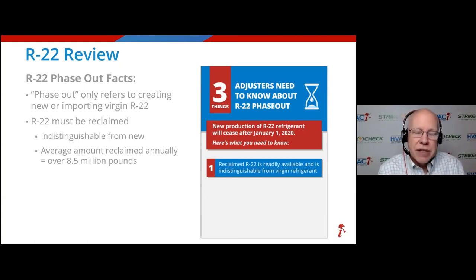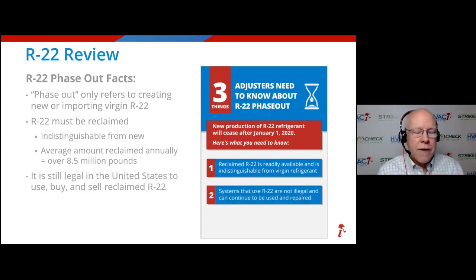So we have a stockpile of R22, 8.5 million pounds a year, as a matter of fact. When we were making it in the United States, we were making about 4 million pounds a year. So we've been reclaiming it higher than making it, even back when we were making it. Per the Montreal Protocol, and this is the kicker right here, it's legal to use, buy, and sell reclaimed R22. All right? We can get it. So when they say they can't get it, they either don't want to get it, they're not looking hard enough, or they want to sell a new system. It's available and you can get it.